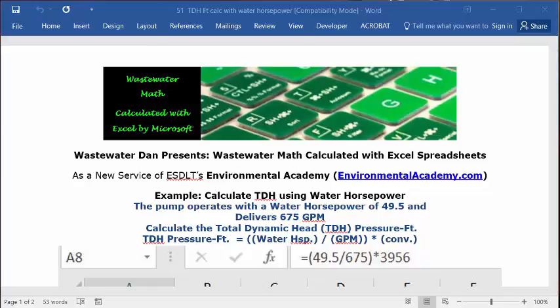Today's example: calculate TDH using water horsepower. The problem reads: the pump operates with a water horsepower of 49.5 and delivers 675 GPM. Now, calculate the TDH, total dynamic head pressure feet.